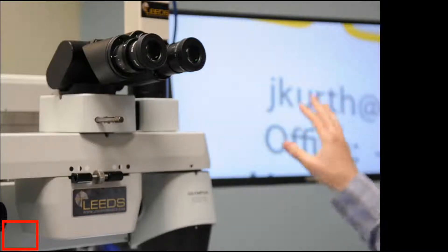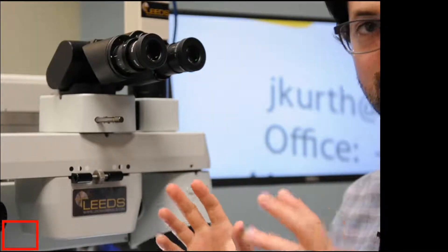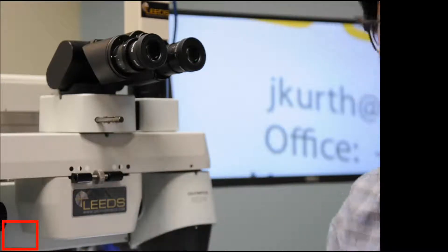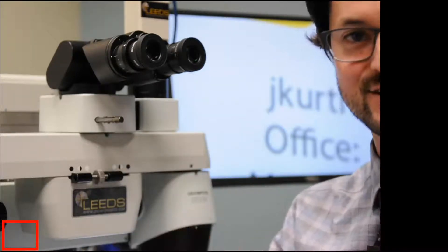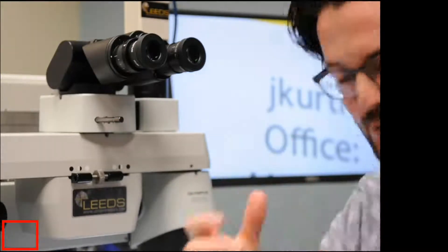It looks okay on the monitor, but to your eyepieces, it's going to be totally different. It shouldn't be in focus at all. If it is, great, you found your diopter correction. It just so happens to be screwed all the way out.